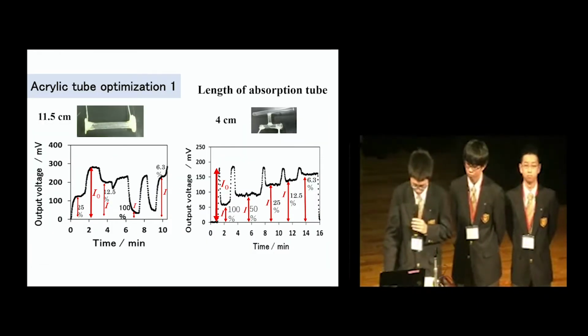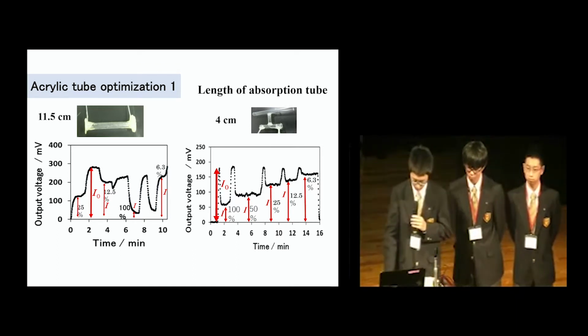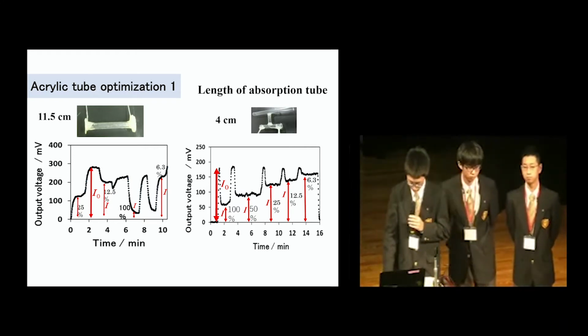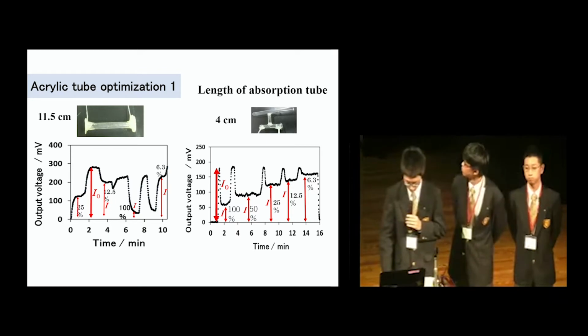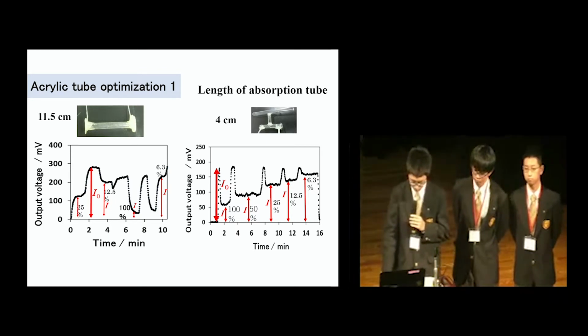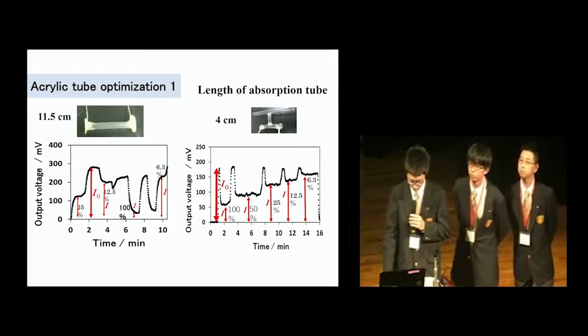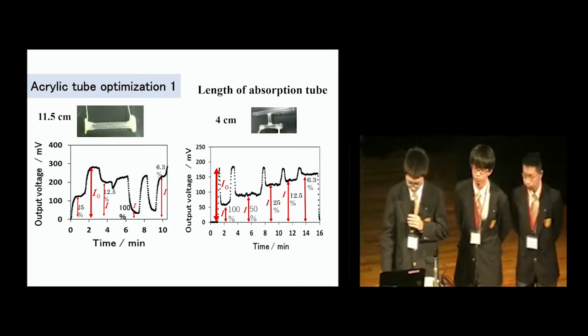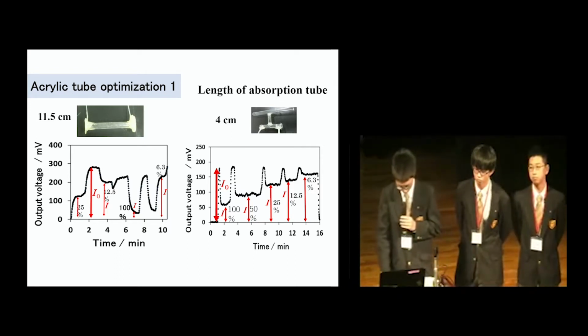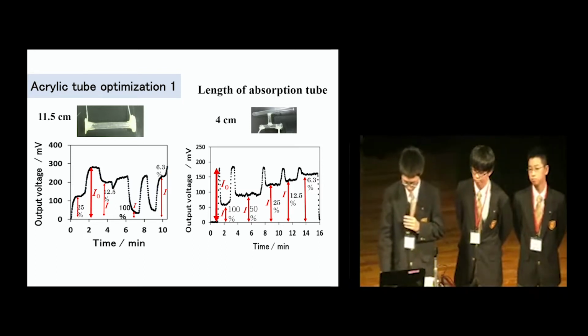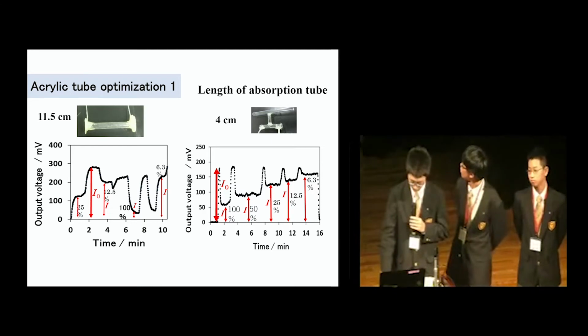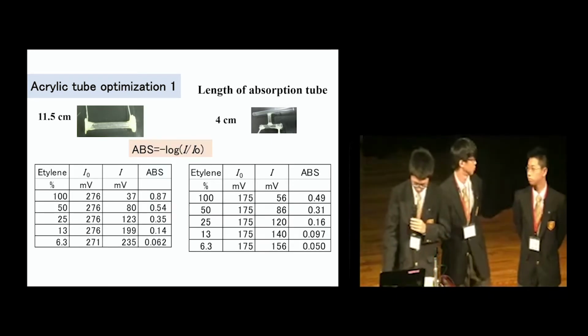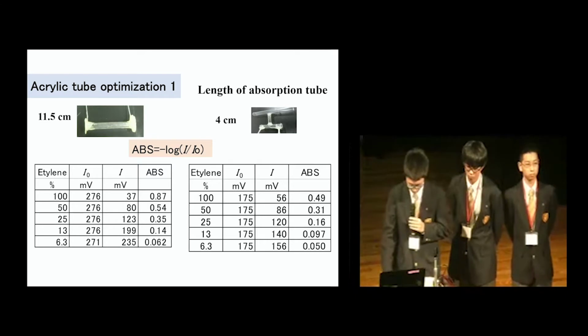First, we used 11.5 cm and 4 cm acrylic absorption tube. Vertical axis was the intensity of infrared light. This is at no ethylene. Incident light intensity I0. Various concentration of standard ethylene gas was put into the tube. This is the transmitted light intensity I. It was smaller than incident light intensity I0. These tables are the results.